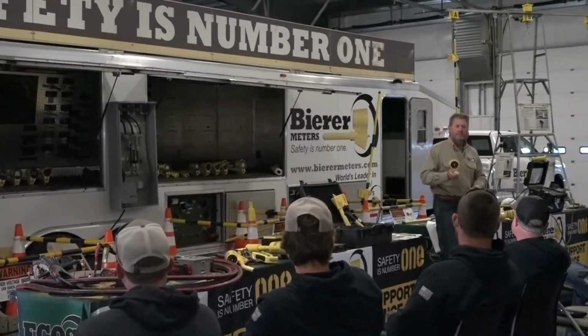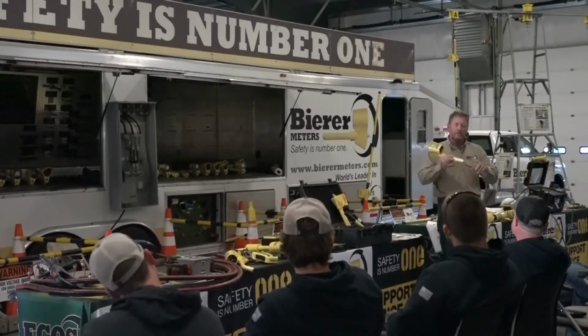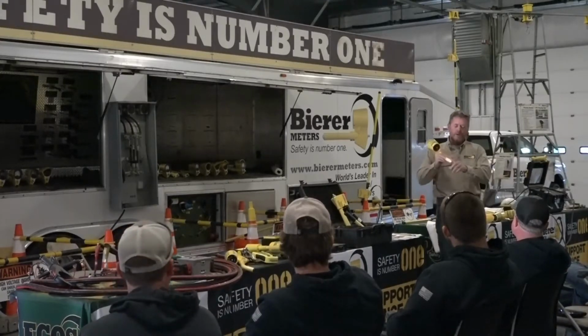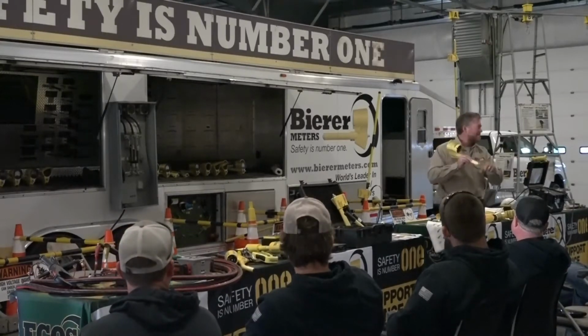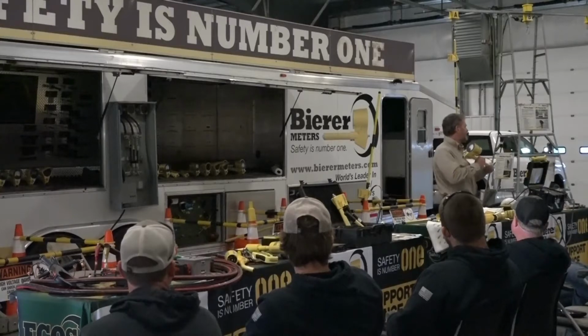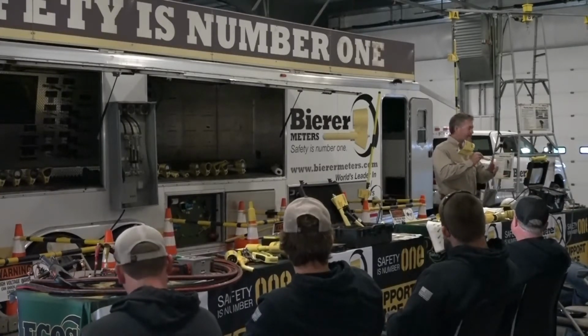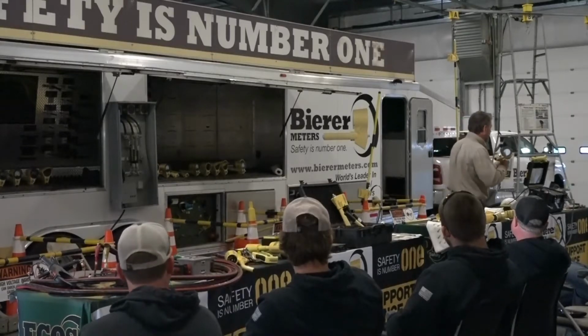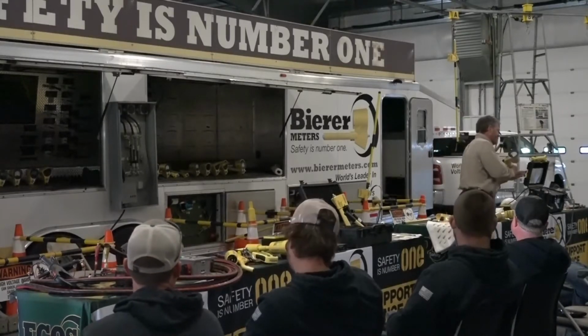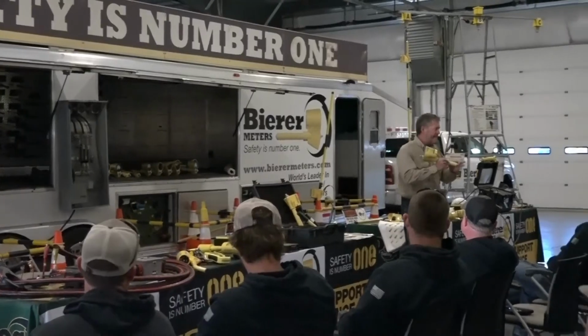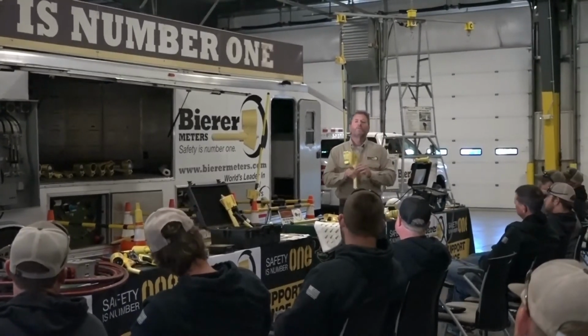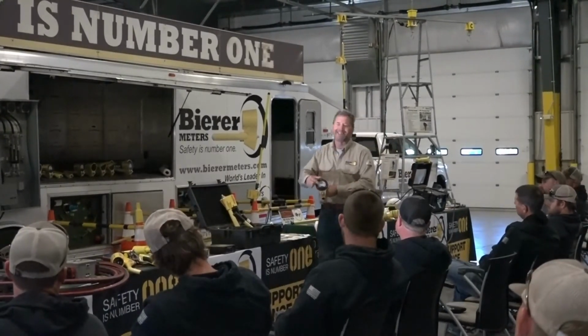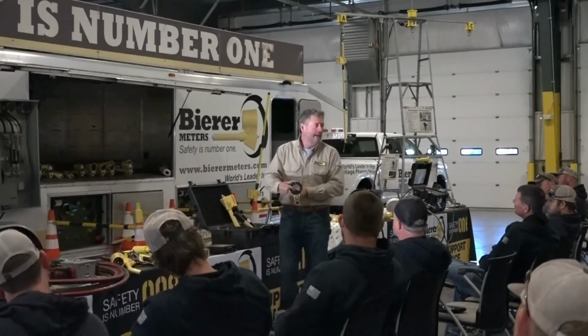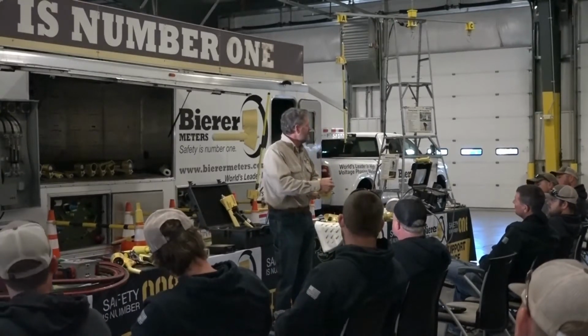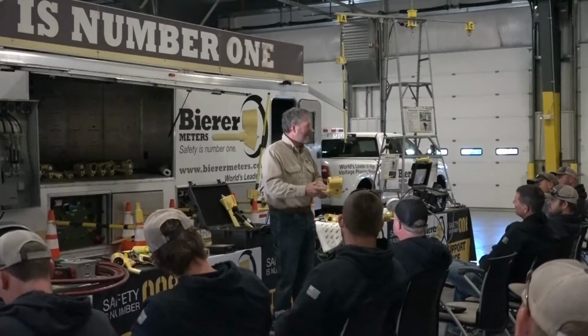When you use these tools on a hot conductor, or even a cold one, we're going to call that X. Energize or de-energize your conductor is X. We're going to create a formulation, an equation. So X is your conductor. If you touch that conductor, you know you have resistors here, but in order for the tool to give you a voltage indication, detection, or reading, it must be energized. It has to be.